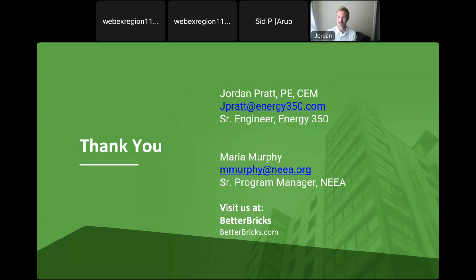And actually, there are a couple more questions, Jordan. How did you decide on 82% efficient? Great question. So the 82% effectiveness that we've landed on was based on quite a bit of research and primarily on the simplification of the system type. So in climate zone 4, where NEEA is very focused, with most of the major population centers in this climate zone, that 82% level at a design winter condition of like 27, 28 degrees will allow the system without any post conditioning to deliver ventilation air at like 62, 63 degrees.